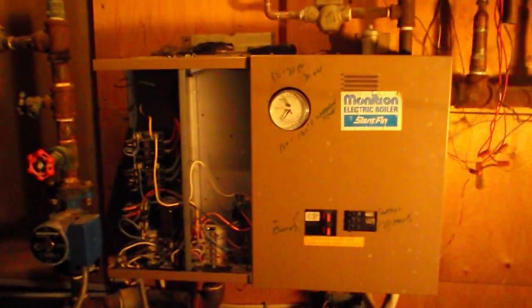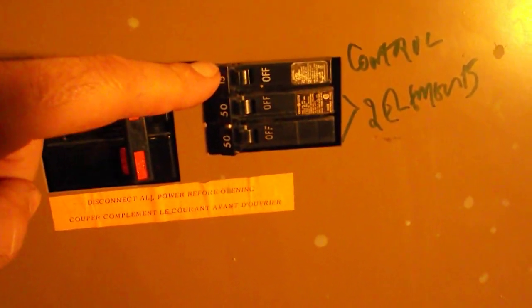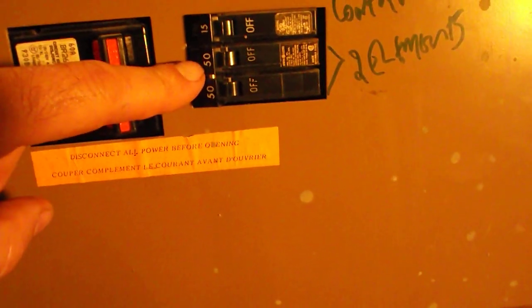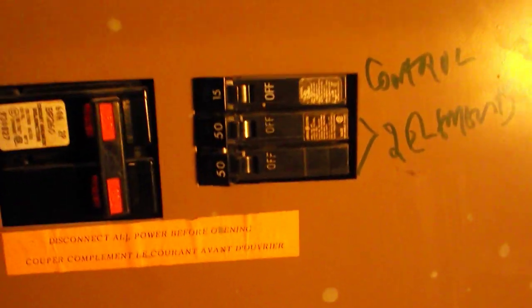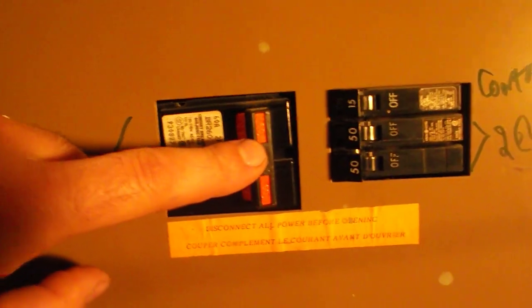So just a real general overview, there's the actual heater. It had a couple of covers, looks like that, and first off there are a couple of breakers in the front. This 15 amp breaker is for control of the relays and the transformer. These twin 50 amp breakers are for the two lower wattage elements. There are four elements in this, two high watt and two low wattage elements. These are for the two lower. These twin 60 amp breakers are for the two high wattage elements.